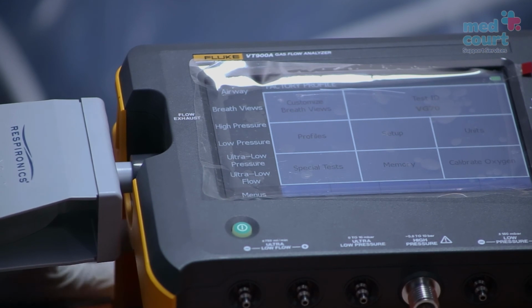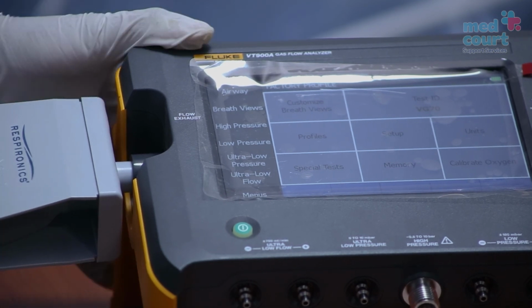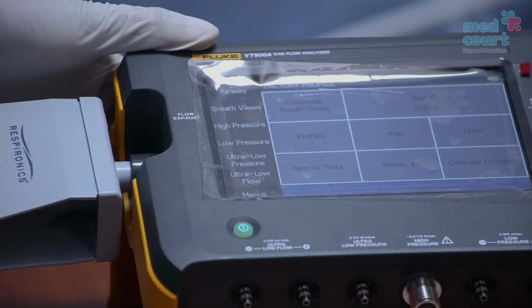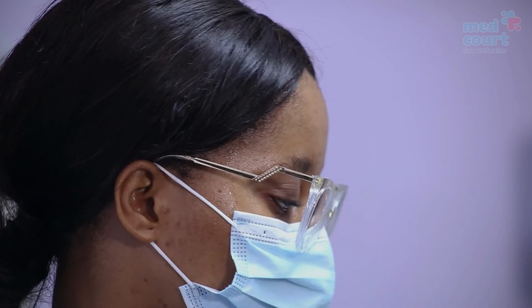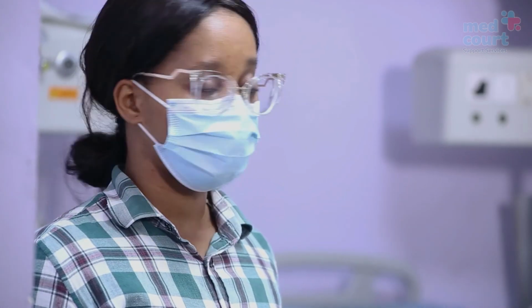And that will be it for the performance verification of the ventilator. Ensure that all readings that are compared on the VT900A are in close value to that of the ventilator. Where there are large gaps, for instance, in the oxygen concentration percentage, check that the oxygen sensor of the ventilator is not expired. If it is, replace it. Also, for the PEEP settings, if the values displayed on the VT900A are very large in comparison to the ventilator settings, change the test lung, as the resistance of the test lung may not be as high as it previously was.